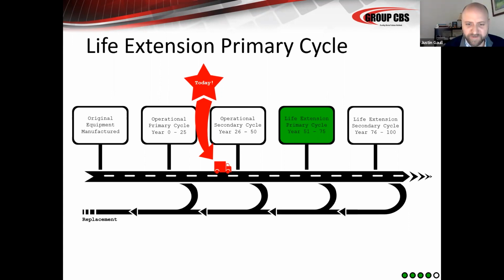I got one more for you there, Finley. As switchgear gets 50 plus years old, is there a concern that inaccessible areas such as line side bus could be experiencing age-related insulation degradation issues? Yeah, we're going to get into that with the non-destructive and online testing techniques. And the line side bus is absolutely sealed off. It's hard to get into. Most people's maintenance cycle doesn't give them enough time to get in there and inspect that properly and clean that. There's ways with partial discharge, there's IR, there's acoustics, there's all kinds of ways to look for corona discharge, to look for partial discharge, to look for that degradation without having to remove those panels.